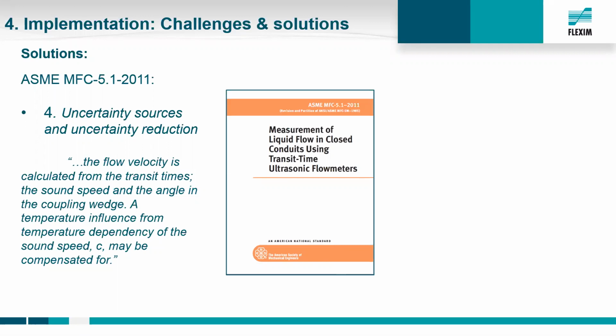Every material has a specific speed of sound, and this changes with temperature. As we remember from the introduction, in transit time technology the measurement of the flow velocity depends on the transit time difference and the acoustic calibration factor. So the K alpha represents the acoustic angle and sound speed. Ambient temperature changes mean also material temperature changes, and transducer wedge temperature changes. This results in changes of the sound speed of the pipe material, of the wedge material, or sometimes also of the fluid. And this raises uncertainty because we are changing the refraction angle, how the signal goes through the pipe and through the fluid. This should be compensated, and ASME described this as well in their guideline, ASME MFC 5.1.